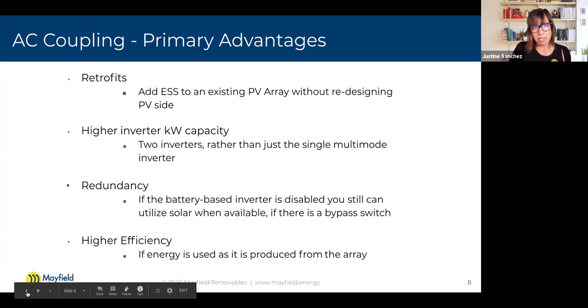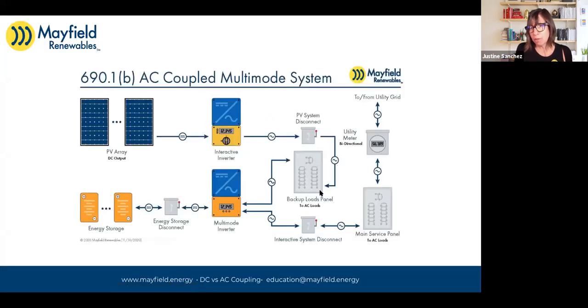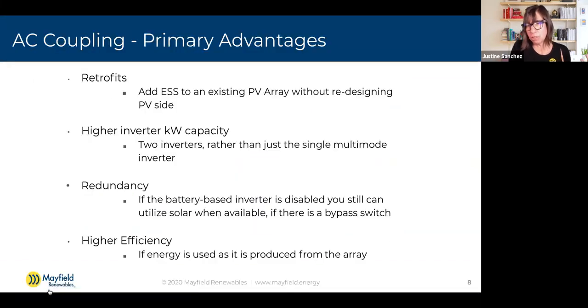One of the advantages of an AC coupled system is that we've got both these inverters feeding this backed up loads panel. Okay, so now we have the kilowatt capacity of this, assuming it's sunny. I mean, it does have to be sunny. You do have to be producing power. And if you're maxing out this inverter with whatever you're producing, then you'll have the full kilowatt rating of that inverter to feed this backed up loads panel. And then down here, if your energy storage system is charged up, and this multi-mode inverter is operating and not in a low voltage situation, which we'll discuss in a moment, we also are utilizing that power into this backed up loads panel. So we have more kilowatt capacity, assuming that the actual energy sources are supplying that capacity to feed our backed up loads panel.